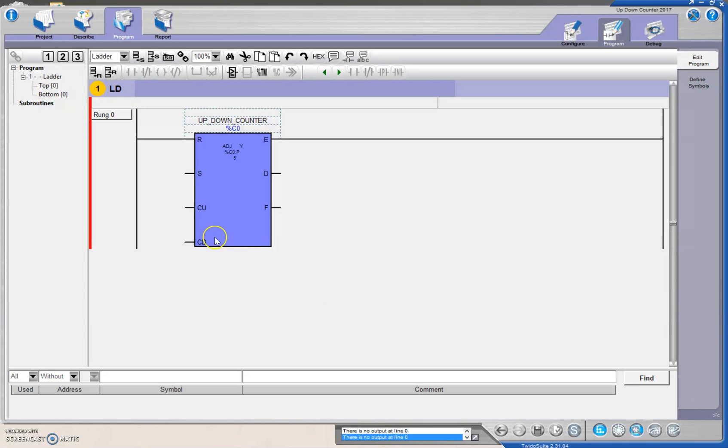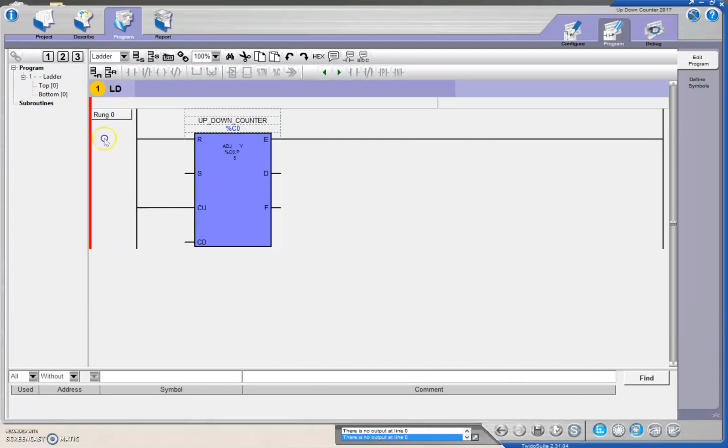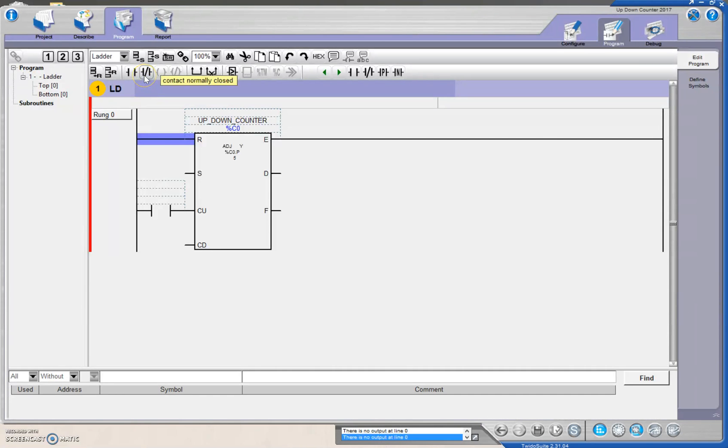What we're going to do is we're going to count up first. I'm going to left click on here and bring a rung over here until I see green. I'm going to drop in an examine if closed there, because I'm going to use a normally open push button. Every time that I close that push button, I'm just going to send a signal into my count up. I have a normally closed contact that I'm going to use for my reset, so I'm going to see when it opens.